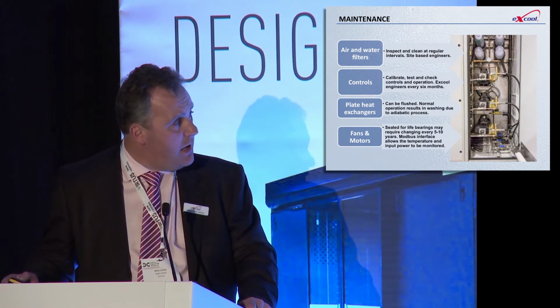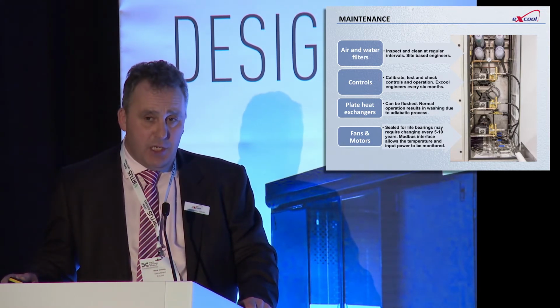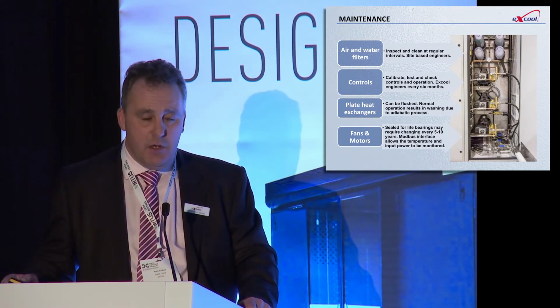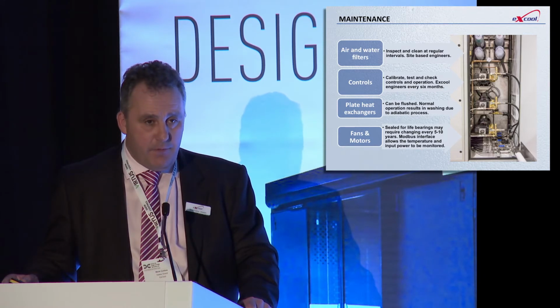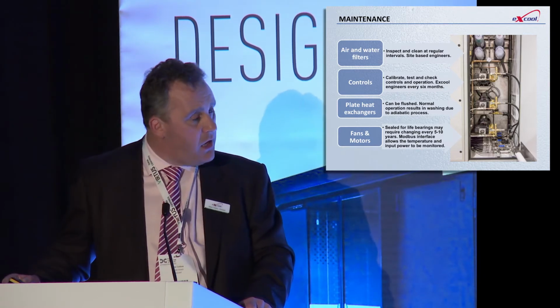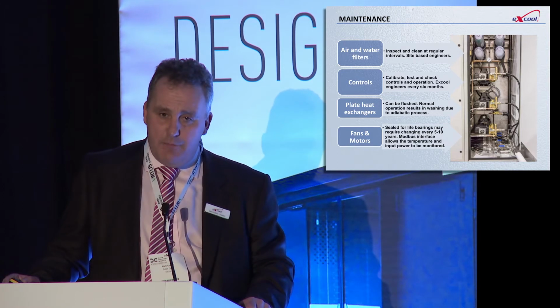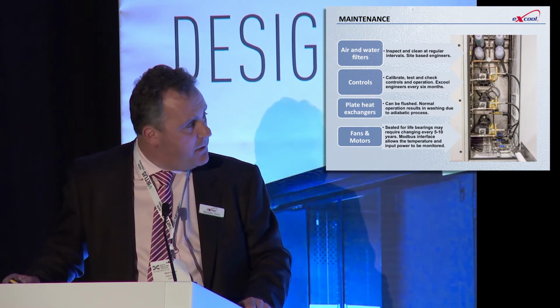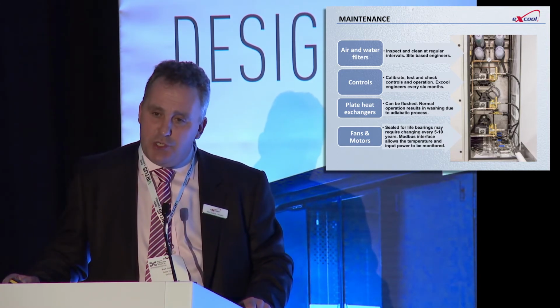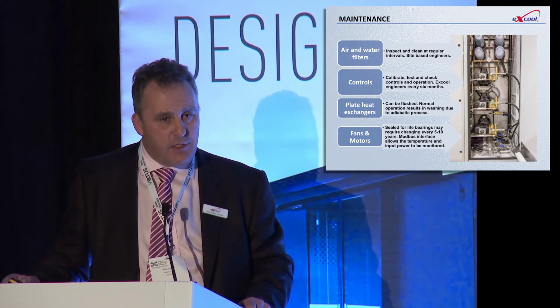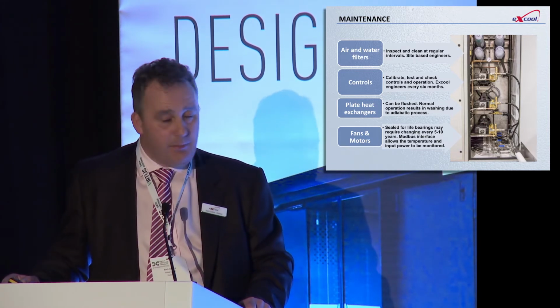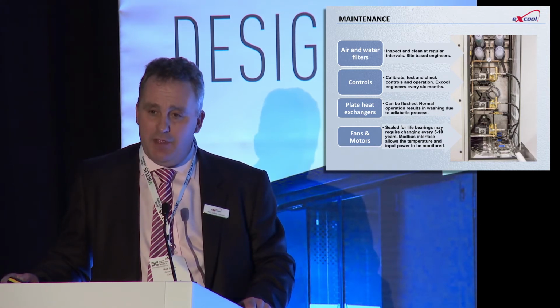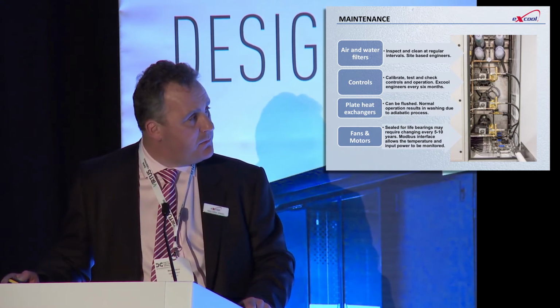And the fans and motors have sealed-for-life bearings, which have a lifespan of between 5 and 10 years, running at 45 degrees C ambient and 100% fan speed. We don't get anywhere near that for any time at all. So the likelihood is that fans and bearings will last for the life of the machine or the life of the data center. But we do monitor the temperature of the bearings and the temperature of the windings remotely for you and issue reports to make sure that we're maintaining healthy conditions on all of those fans and motors.